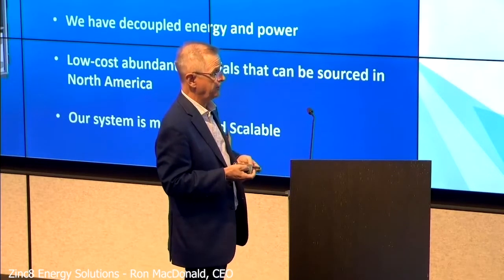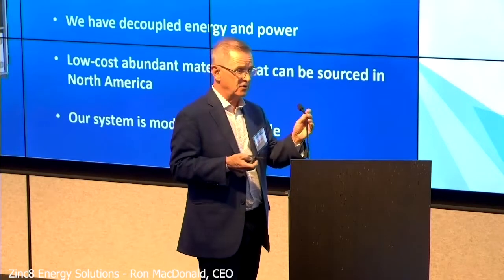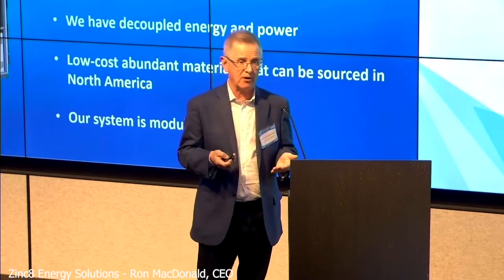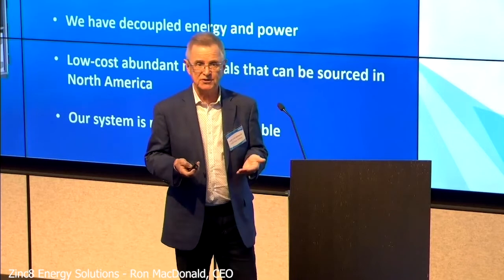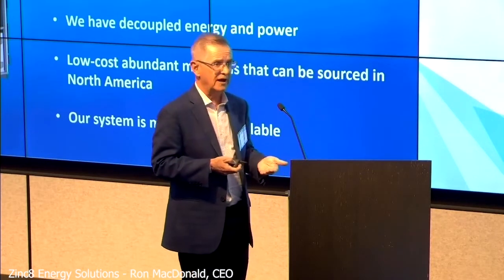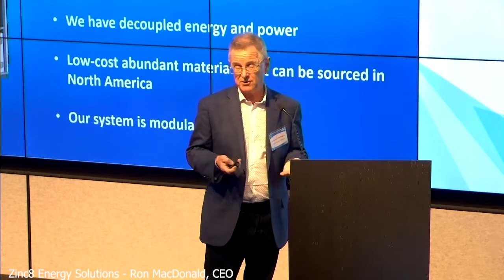Now, what's unique about us? We have decoupled energy and power. So most of the systems that you would be aware of, like say a lithium ion, they haven't decoupled the energy and power. So it's a 1-to-1 ratio. So if you got 20 kilowatts of power, you can only store 20 kilowatts of energy. If you want to double the amount of energy you store, you have to double the amount of power stacks that you have, even though you probably don't need the power.